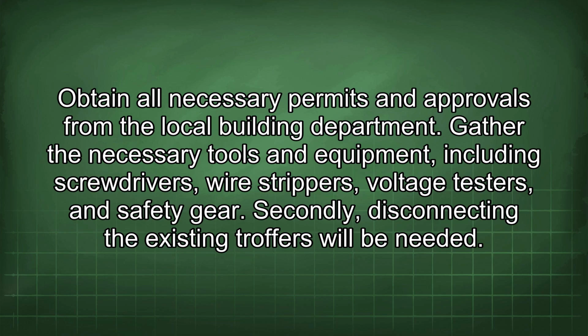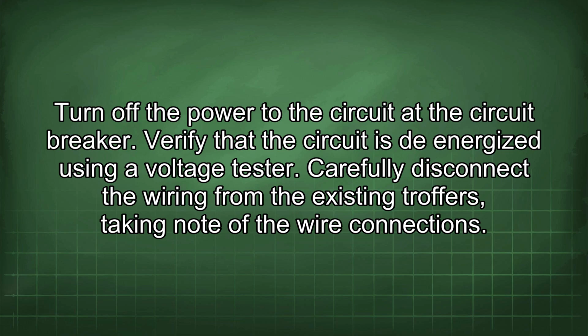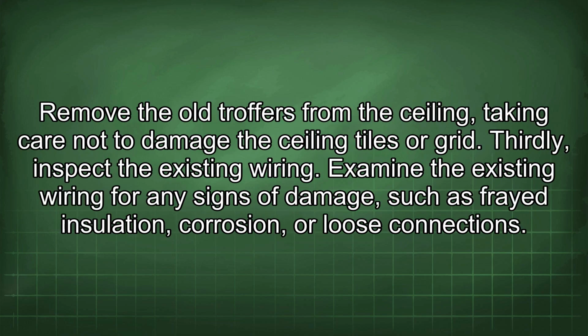Secondly, disconnecting the existing troffers will be needed. Turn off the power to the circuit at the circuit breaker. Verify that the circuit is de-energized using a voltage tester. Carefully disconnect the wiring from the existing troffers, taking note of the wire connections. Remove the old troffers from the ceiling, taking care not to damage the ceiling tiles or grid.